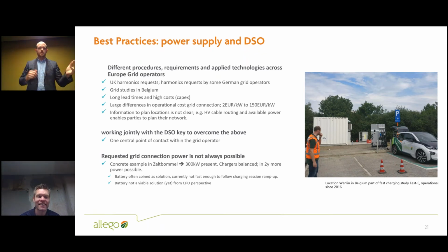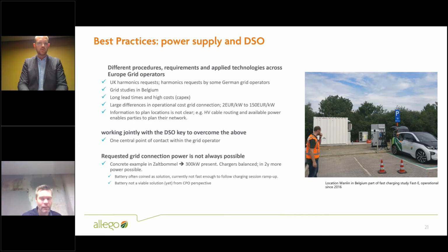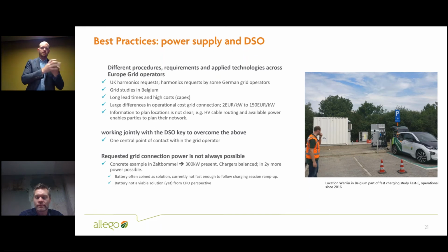There are many different procedures from a grid operator perspective, with different requirements or applied technologies for grid protection across Europe. In the UK, for example, there's a default request for a harmonics report on the specific charger used. In Germany, some grid operators request it and reject a specific charging solution, while others accept the same solution with the same harmonics report. So it's still not 100% clear what the boundaries are in Germany for when a charging solution can be used.